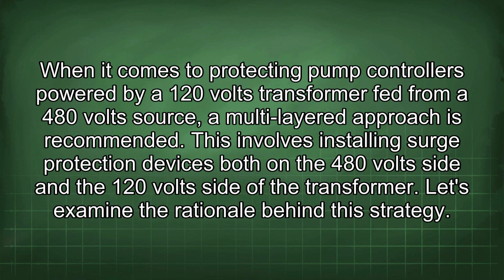When it comes to protecting pump controllers powered by a 120 volts transformer fed from a 480 volt source, a multi-layered approach is recommended. This involves installing surge protection devices both on the 480 volts side and the 120 volts side of the transformer. Let's examine the rationale behind this strategy.